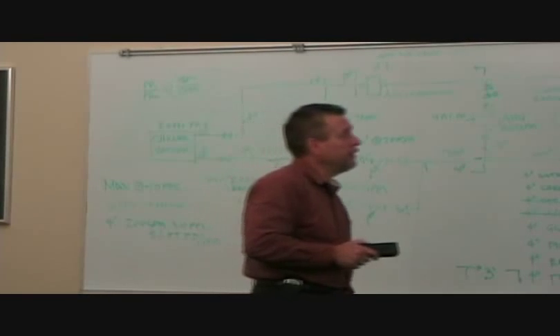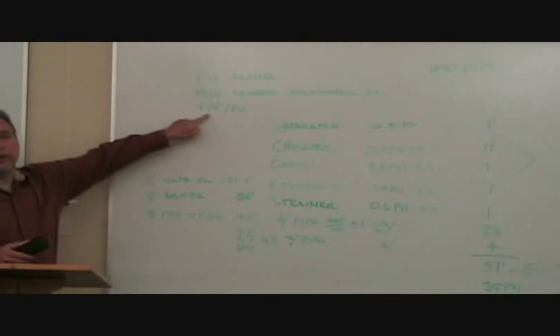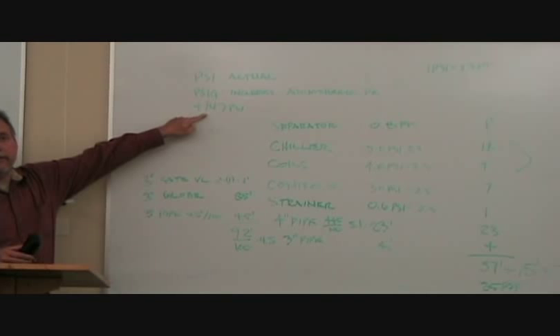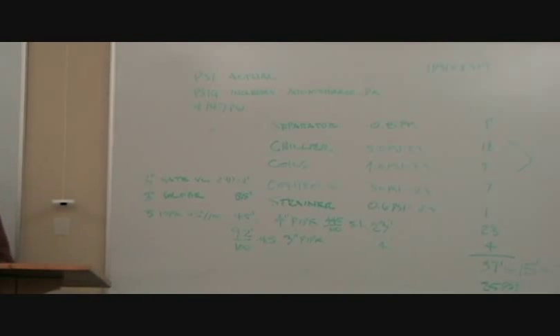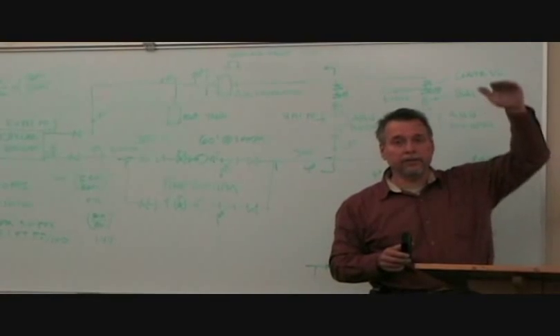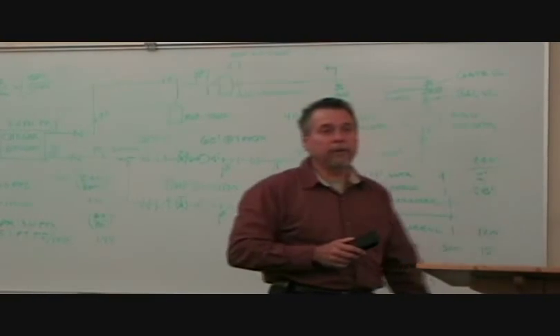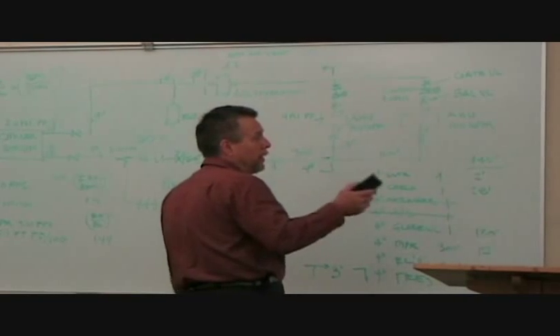Again, because you calculate this as gauge pressure too. So you start out with 14.7 pounds, even at the same elevation. And you start subtracting your pipe losses. So whatever your pipe losses are, it's just how much you set that cooling tower above the pump. We'll talk about that Thursday.